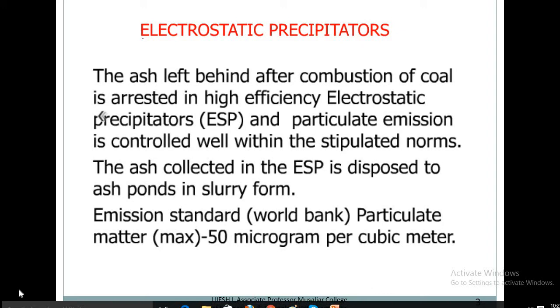Now we will look at electrostatic precipitators. The ash left behind after combustion of coal is arrested in high-efficiency electrostatic precipitators (ESP). Particulate emission is controlled well within the stipulated norms. The ash collected in the ESP is disposed of in ash ponds in slurry form. The emission standard for particulate matter is 50 micrograms per cubic meter.